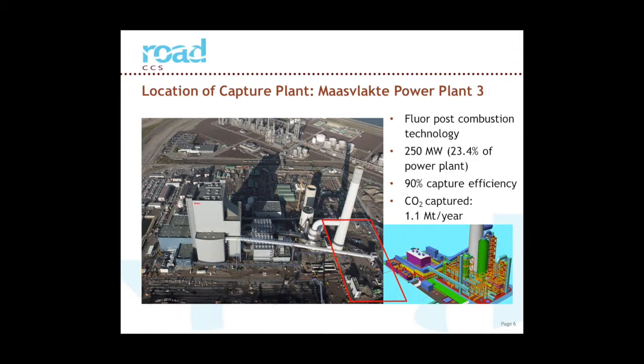I think, what else do I need to say about that? I should say something about the stack and the cooling system. There's no gas heater in this plant. It has a wet stack, so the flue gas coming in from the boiler gets quenched in the FGD and then comes up here at about 50 degrees and goes into the stack. And our flue gas tie-ins for the capture plant will be in the stack.